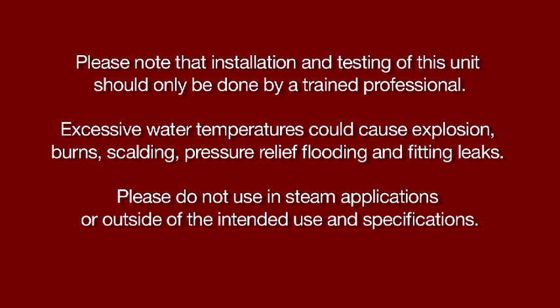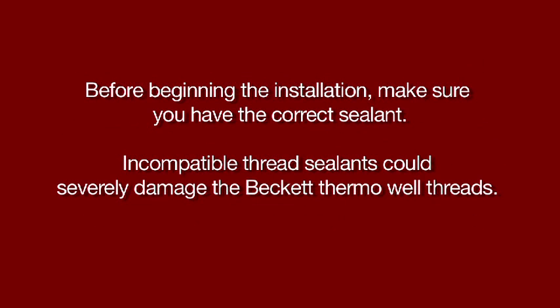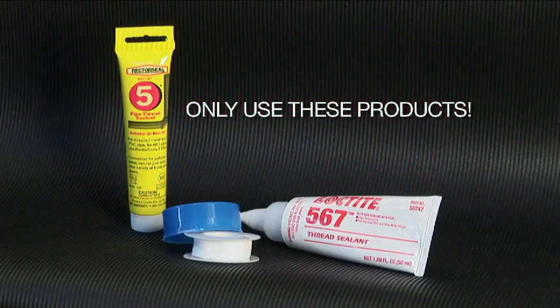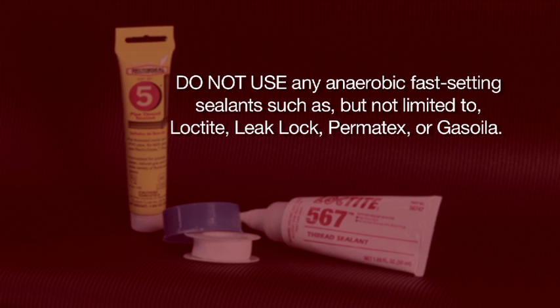Please do not use in steam applications or outside of the intended use and specifications. Before beginning the installation, make sure you have the correct sealant. Incompatible thread sealants could severely damage the Beckett thermowell threads. Only use Teflon tape or Rectorseal No. 5 soft set. Loctite 567 is the only Loctite product that can be used. Do not use any anaerobic fast setting sealants such as, but not limited to, Loctite, Leak Lock, Permatex, or Gasoila.